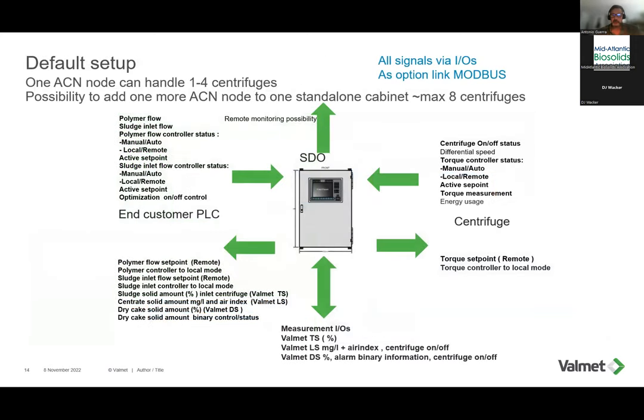If you look at the setup here, customers will be asking how difficult this is to implement. Obviously a bunch of signals need to be implemented. All signals are typically done through normal IOs through the customer's existing PLC or control system, and there's also an availability to use Modbus to get all those inputs and outputs. If you look at those signals coming in, we need to know the polymer flow, the sludge flow, the status of the controller for the polymer flow and so forth. That is the data that the customer's PLC is providing to us. Then we're controlling through the IOs what I just mentioned: we're controlling the set point of the polymer, we're controlling how much flow is coming into the system and so forth. Basically, those are the various signals that need to be coming in and out of the system through the SDO control box.